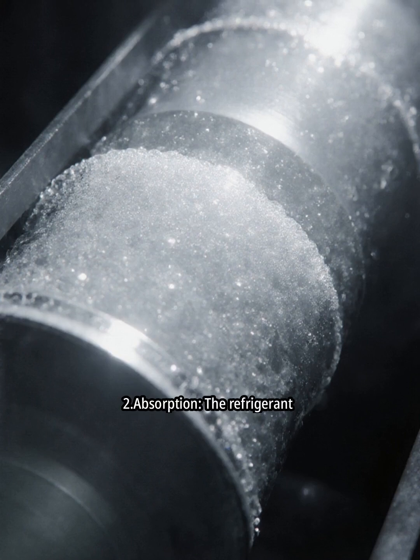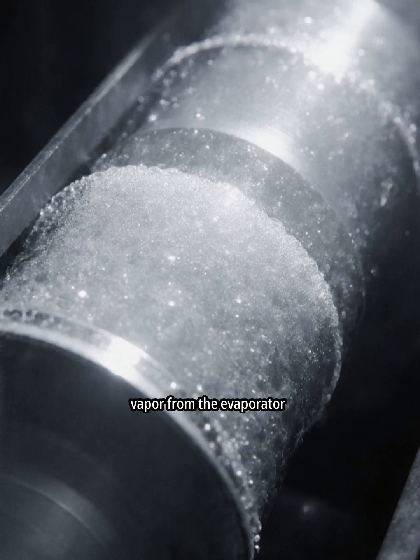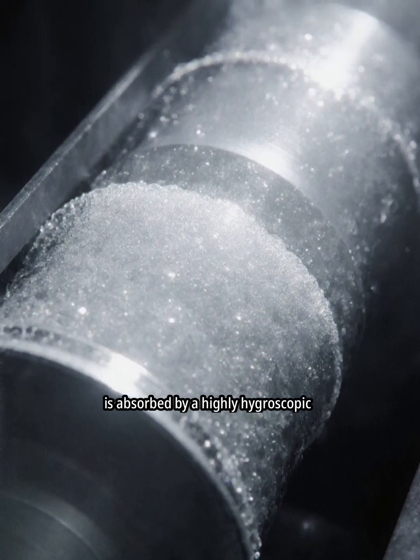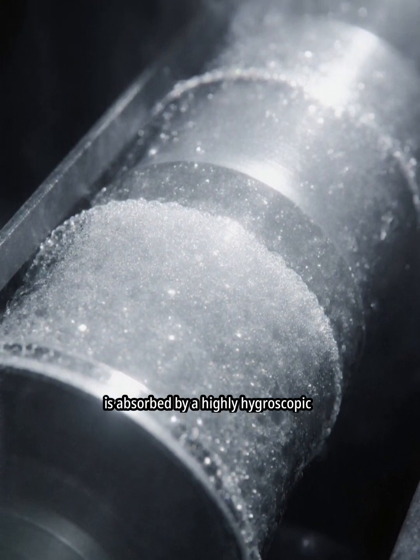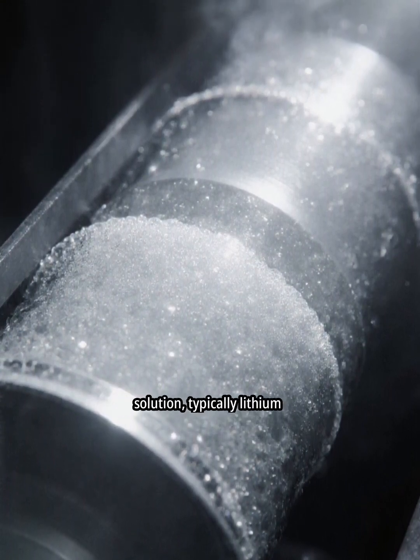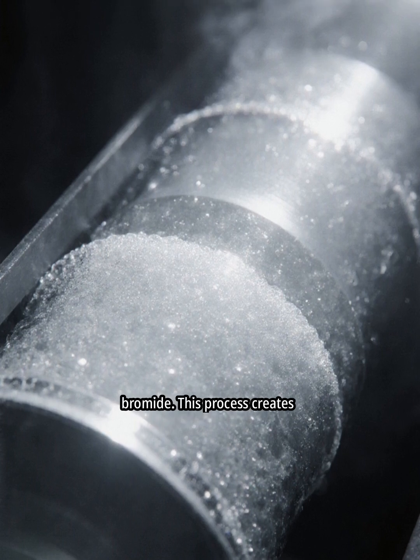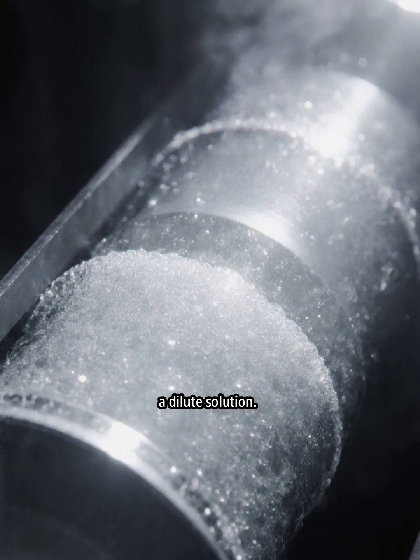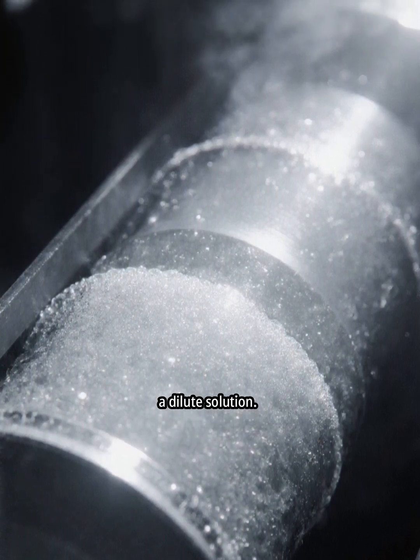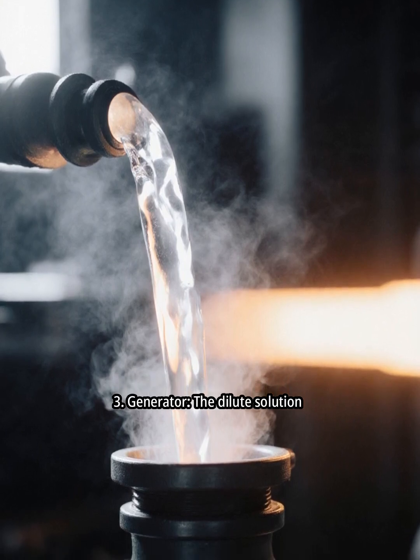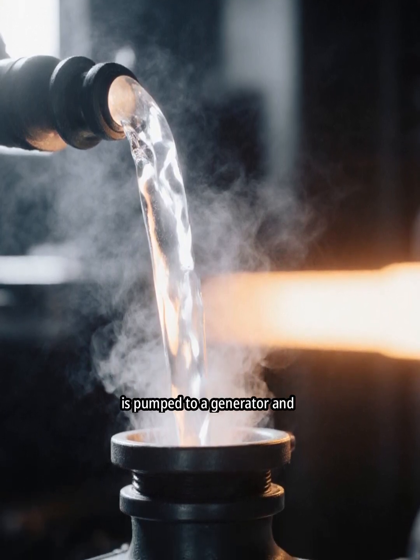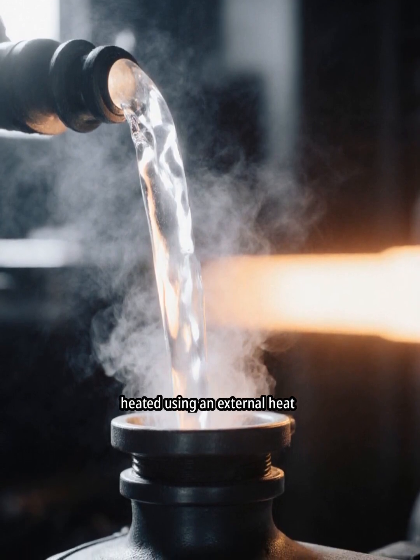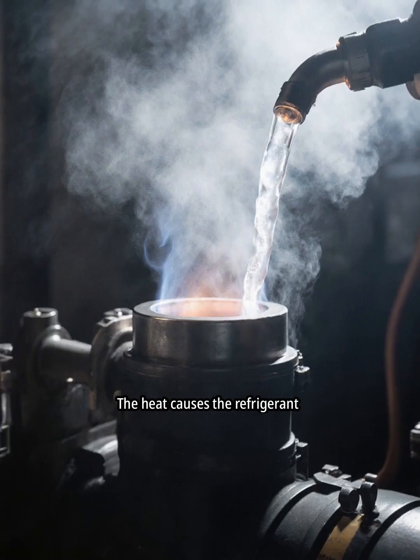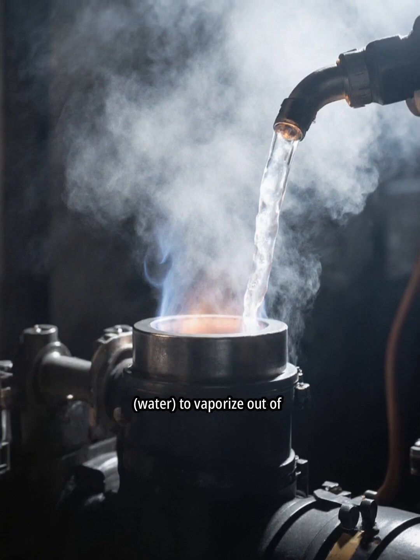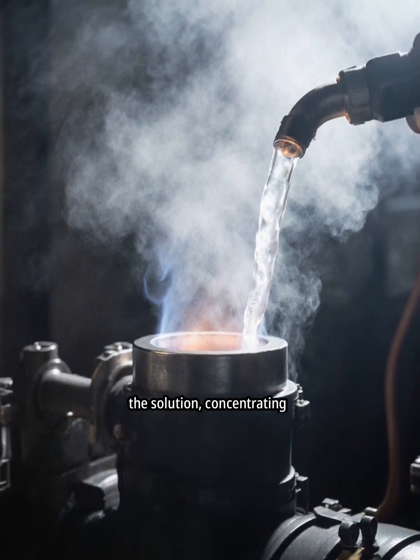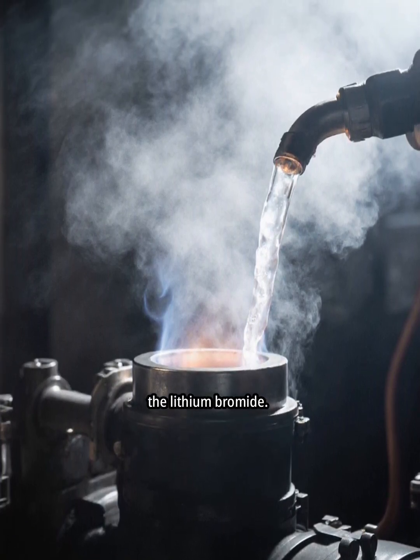process water. 2. Absorption. The refrigerant vapor from the evaporator is absorbed by a highly hygroscopic, water-attracting, absorbent solution, typically lithium bromide. This process creates a dilute solution. 3. Generator. The dilute solution is pumped to a generator and heated using an external heat source. The heat causes the refrigerant, water, to vaporize out of the solution, concentrating the lithium bromide.